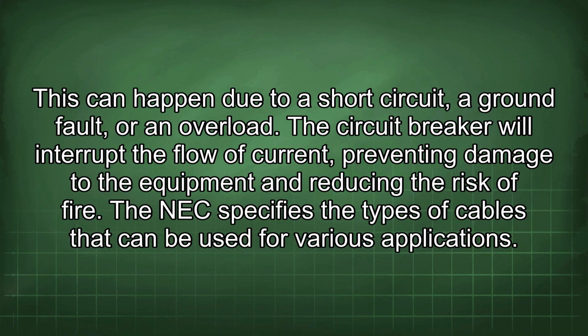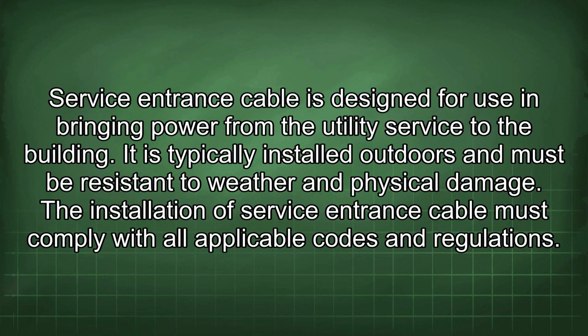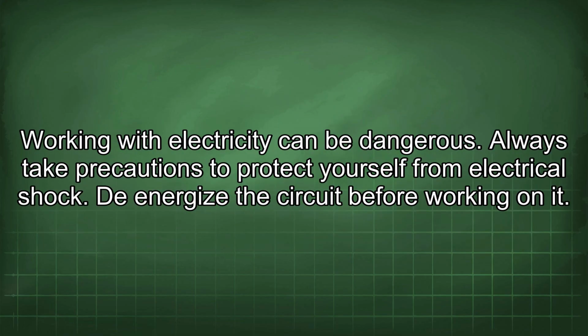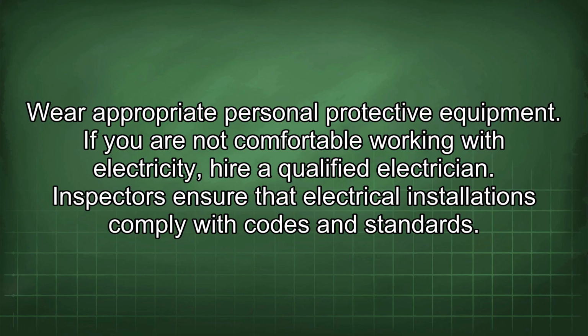The NEC specifies the types of cables that can be used for various applications. Service entrance cable is designed for use in bringing power from the utility service to the building. It is typically installed outdoors and must be resistant to weather and physical damage. The installation of service entrance cable must comply with all applicable codes and regulations. Working with electricity can be dangerous. Always take precautions to protect yourself from electrical shock. De-energize the circuit before working on it. Wear appropriate personal protective equipment. If you are not comfortable working with electricity, hire a qualified electrician.